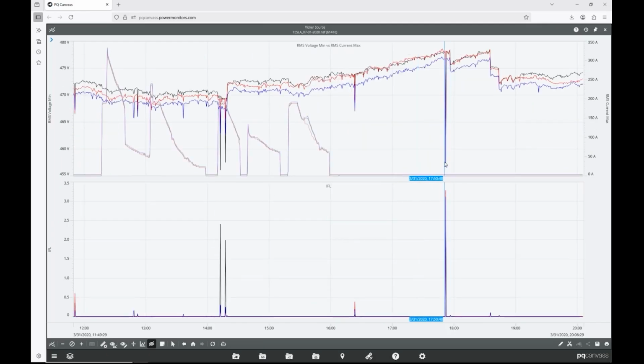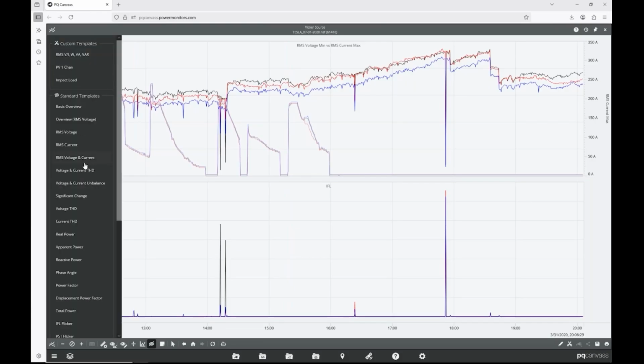And what we see for voltage is we have voltage sags that aren't really correlated with the current. The current is not causing these voltage sags. So in this location, the rapid changes in current are not causing rapid changes in voltage. This is a fairly strong system and a large transformer. If you have a weak system, the effects could be more significant. So that is something to look out for because you have these abrupt increases in current. That's the potential for a rapid voltage change, which could lead to flicker.